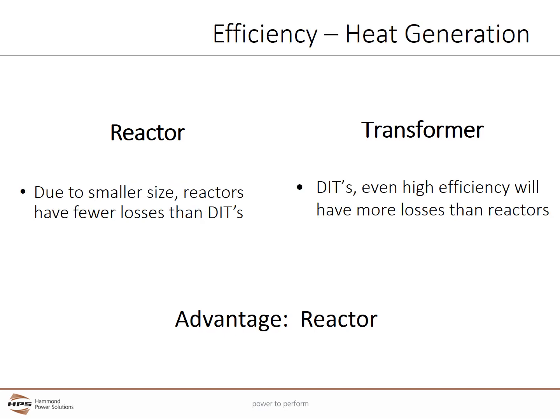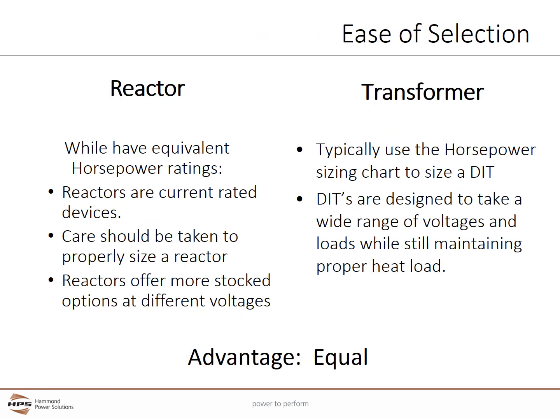Efficiency and heat generation. Due to their small size, reactors have fewer losses than their much larger equivalent transformers. As a result, reactors generate less heat than the equivalent transformer. In this case, the advantage goes to the reactor. Ease of selection. Both transformers and reactors have their advantages. Reactors are more flexible to choose an impedance, while transformers can change the voltage and use taps to tune for local voltages. When the user understands how to initially select either a reactor or a transformer, the remaining steps to select a proper reactor or transformer part number is relatively easy. As a result, both reactors and transformers are tied for ease of selection.